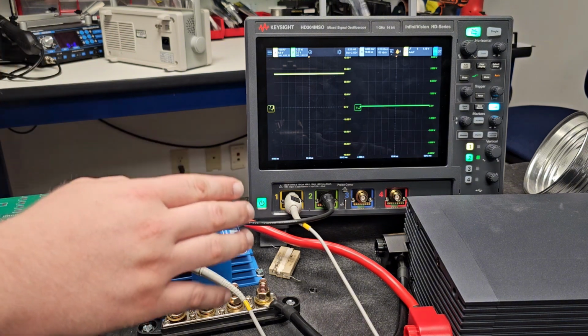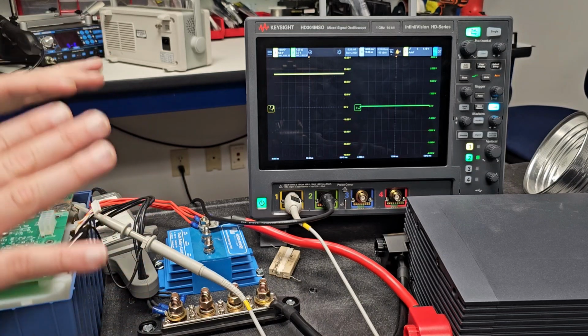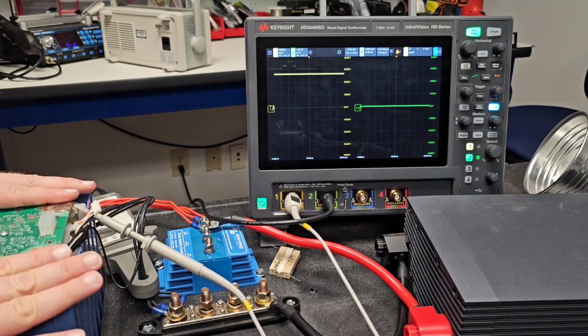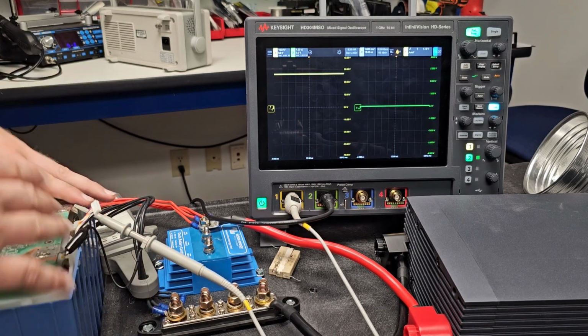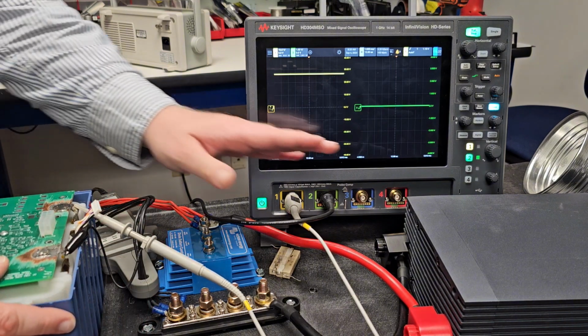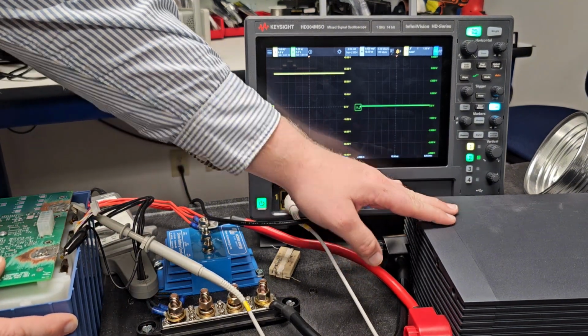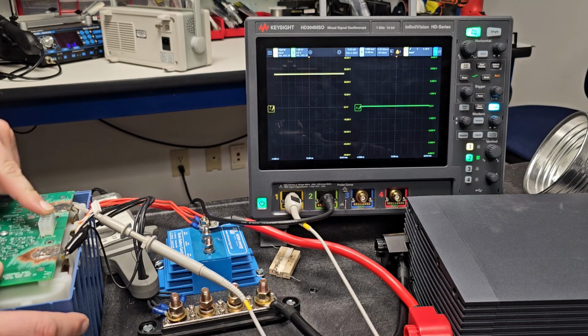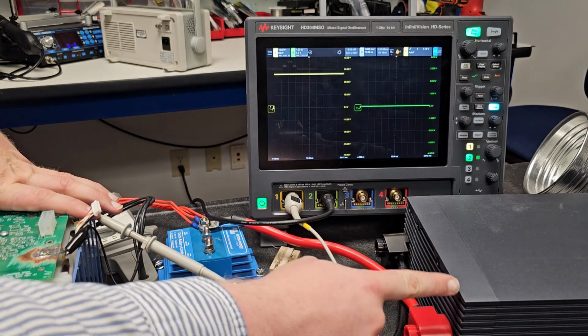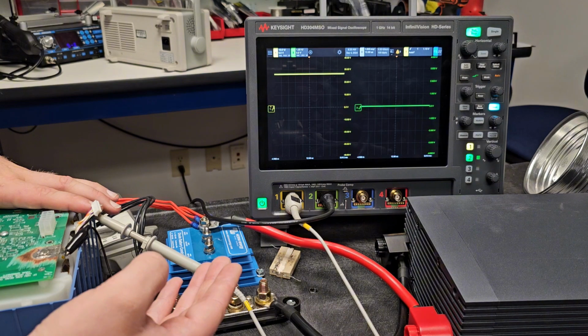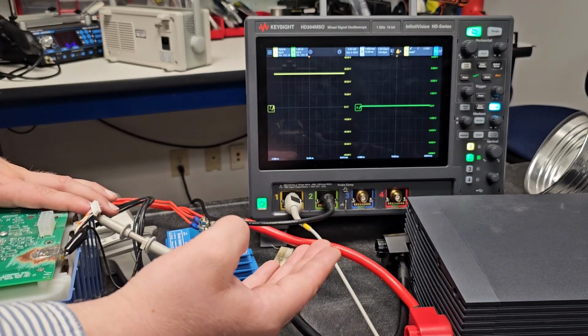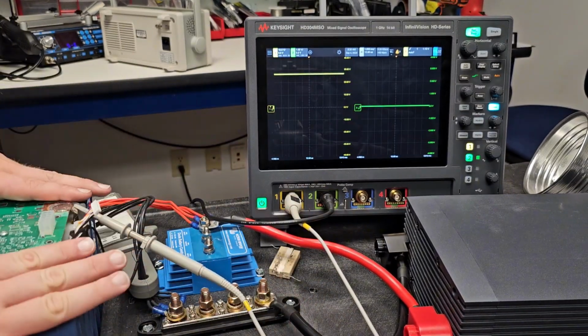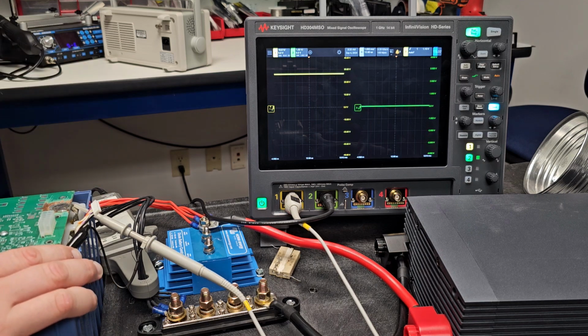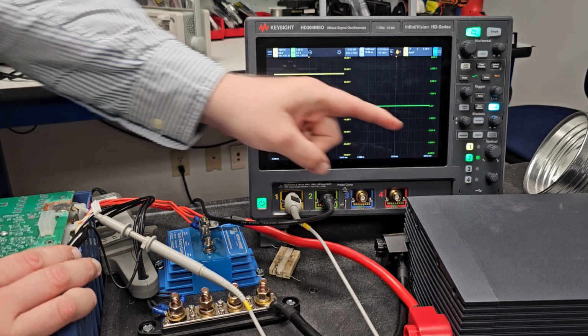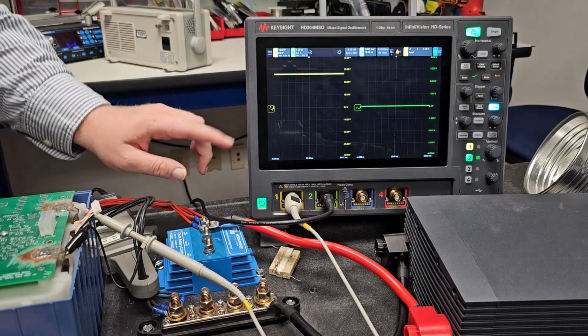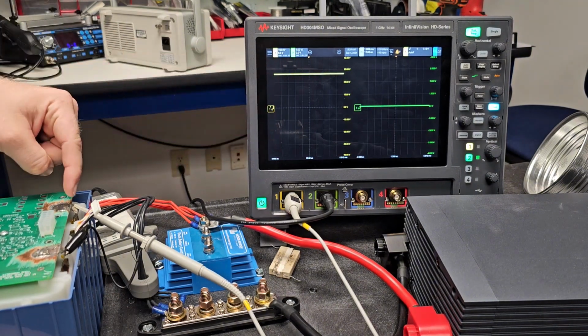But I have this setup here. So the problem I have a lot of times with batteries is surge current. So it's not continuous current, but it's surge current. So this is a 24 volt Samlex inverter, and this is a 24 volt battery pack. Well, the problem is this inverter has huge input capacitors and then huge output capacitors on the AC side. So we have to make sure we set the BMSs to where their trip limits won't trip whenever this is initially starting up. So I have channel 1 here set up to monitor the battery pack voltage.